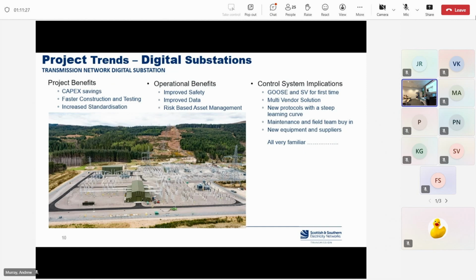Some of the benefits we're looking for are CapEx savings, such as reduction of the copper hardwired signals within the substation, faster construction and testing, especially around FAT and site acceptance testing for digital signals like Goose and sample values, plus improved safety and data, with even more signals available.